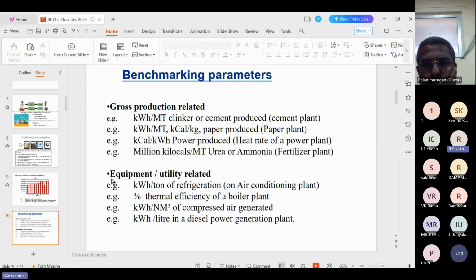For AC measurement, kWh, that is unit consumption per TR, is the rated benchmarking parameter. And kWh per Nm cubed, normal meter cube, is used for the compressed air generator, but practically we have seen people telling us CFM, that is cubic foot per minute. So kWh per CFM is now followed in most industries for compressed air. Another classic example is for DG sets: how many units were generated per liter? It is called UPL, units per liter, nothing but kWh per liter.